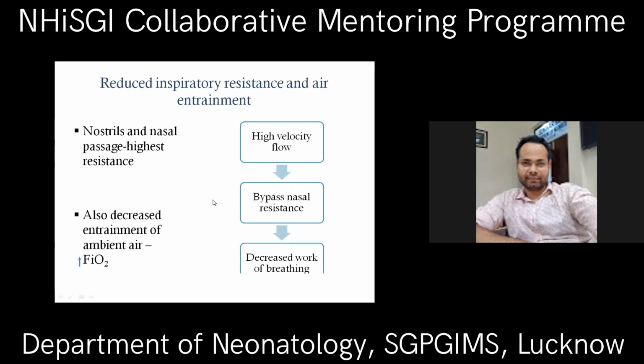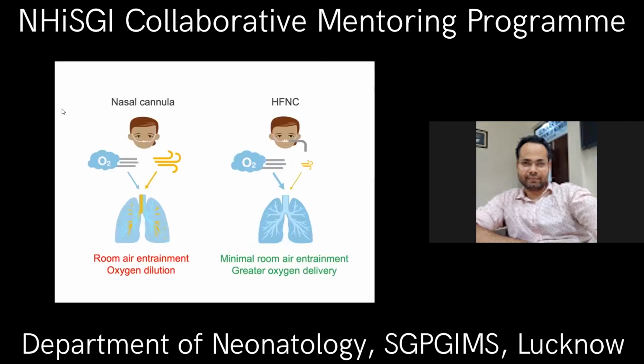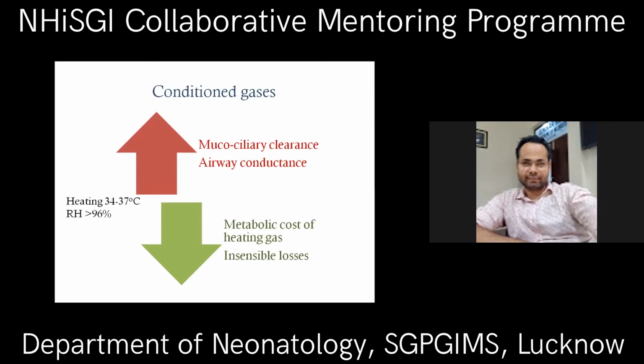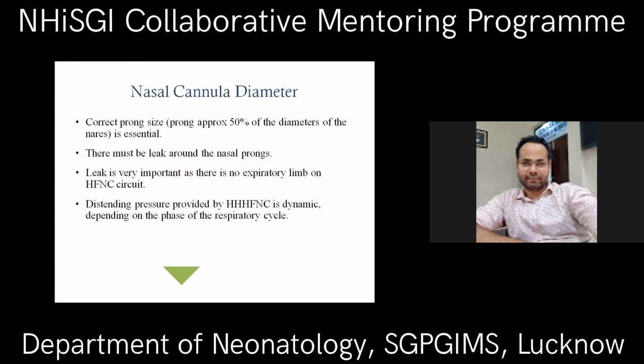It also causes decreased entrainment of the ambient air. When we use a normal low flow nasal cannula, we can see that oxygen and air both are entering via the nostrils into the lungs, but with HFNC there is less entrainment of room air and more oxygen delivery. And with the use of conditioned gases, there is better mucociliary clearance. There is better airway conductance because desiccation of the mucosa is less, and also with heating to 34 to 37 degrees and relative humidity more than 96%, there is less insensible loss because some water would have been lost in humidification of the gas in the trachea. So that water loss is not there, and the metabolic cost of heating the gas is also reduced because the air is already heated and humidified.